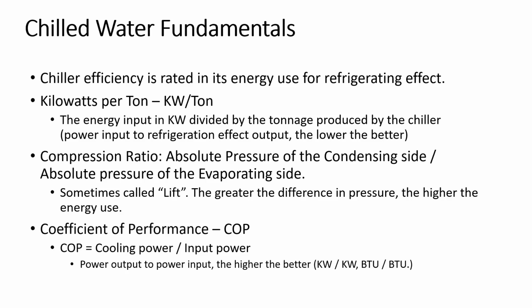Another way of rating how efficient your machine is compression ratio. Sometimes it's now being called lift. You know, when somebody says that, I look at them like, what are we lifting? But it's the difference between the high side and the low side pressure in absolute pressure, not gauge pressure, because a lot of machines work in a vacuum. They'll actually pull a vacuum on the low side. You need an absolute pressure in order to do the calculation. So we use absolute pressures to compare. Now, these can be 2 to 3 also. The lower the compression ratio, the better. That means that your machine's not working so hard to produce the same refrigerating effect.